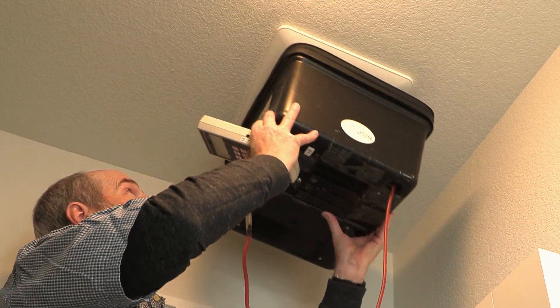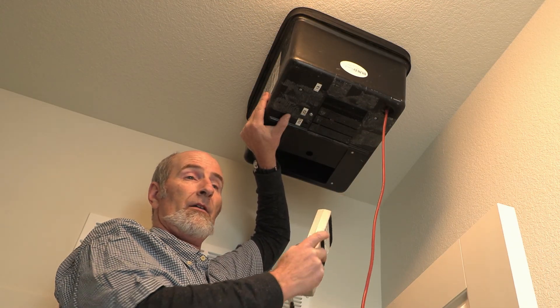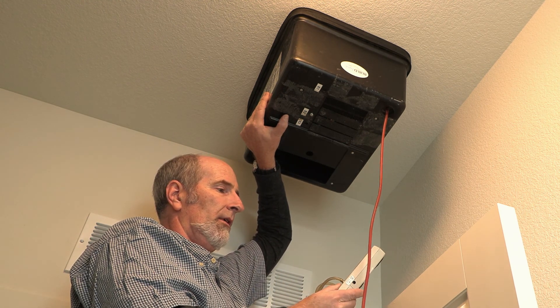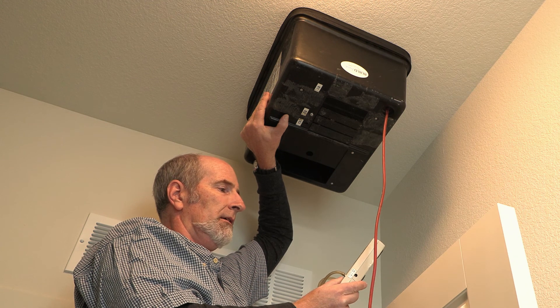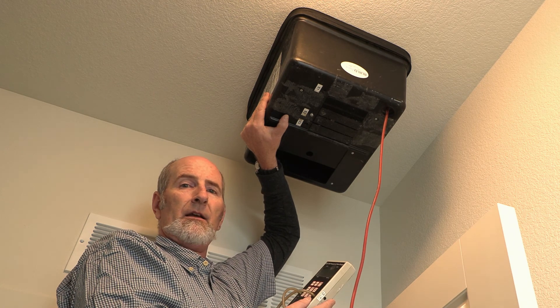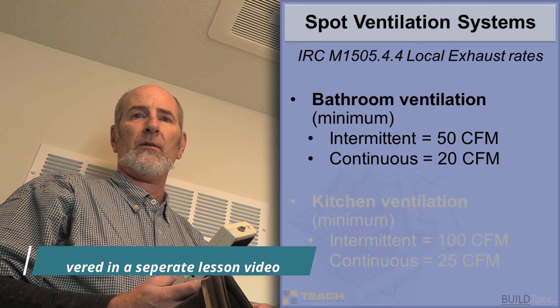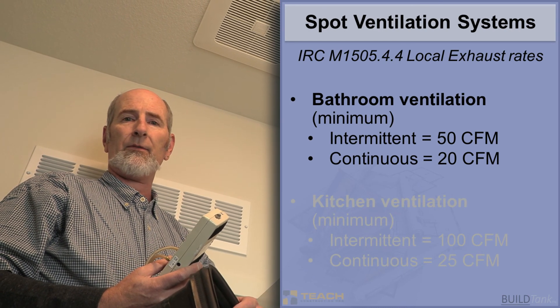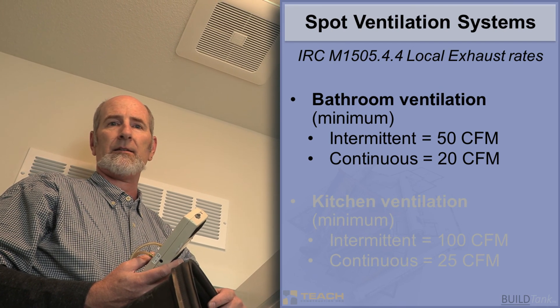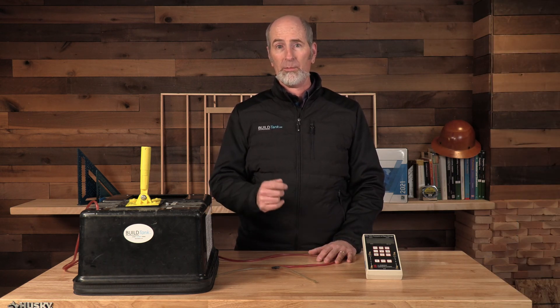To do the test, I hold the flow box tight against the drywall over the fan and measure the flow of air through the known opening in the box. We're measuring about eight pascals of pressure inside the box, giving us a flow measurement of about 59 CFM. This fan happens to be part of an exhaust ventilation system, so we'd take that 59 CFM to the ASHRAE 62.2 table to see if it's sufficient. But if this were a bathroom fan, it is passing at 59 CFM. Just another tool in our arsenal to build better — I hope to see you in the field using it.